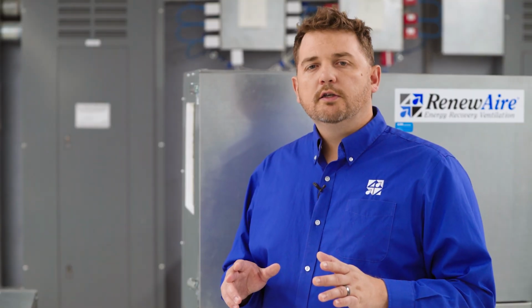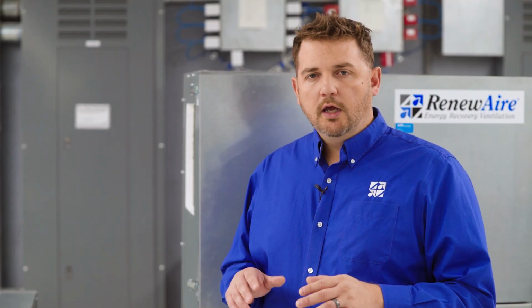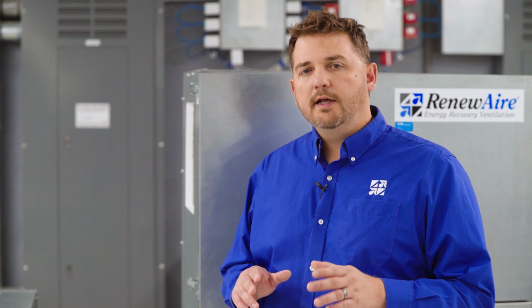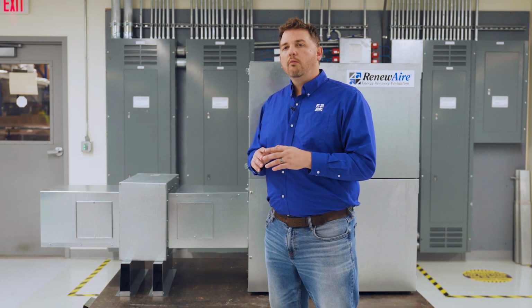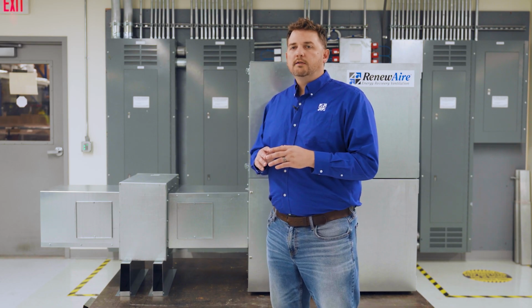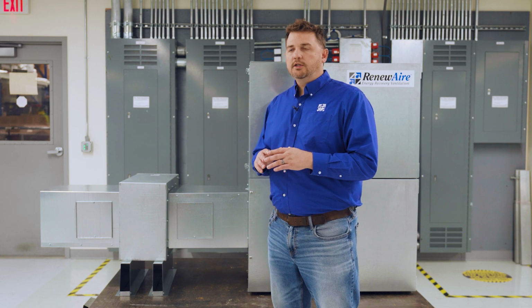Now let's move on to the structural support of this option. These coil modules are relatively heavy, upwards of 100 pounds in some scenarios. It is important to structurally support the coil module as opposed to relying solely on the ductwork to support the coil in place. This can be accomplished by hanging the coil via duct hangers or placing the coil on a solid surface or base during installation, as we have shown.